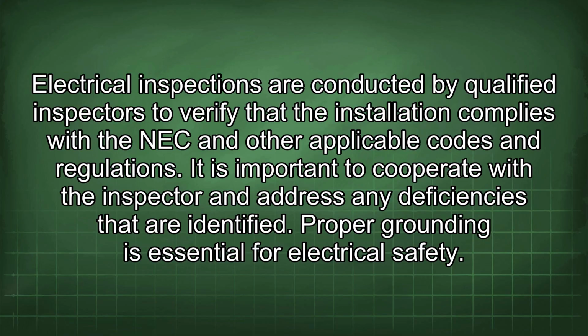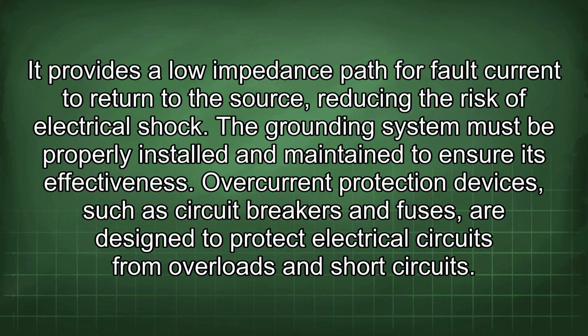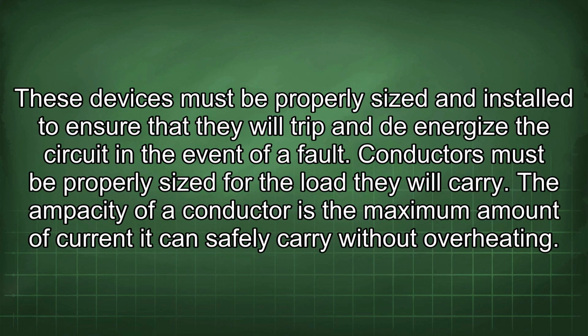Proper grounding is essential for electrical safety. It provides a lower impedance path for fault current to return to the source, reducing the risk of electrical shock. The grounding system must be properly installed and maintained to ensure its effectiveness. Overcurrent protection devices, such as circuit breakers and fuses, are designed to protect electrical circuits from overloads and short circuits. These devices must be properly sized and installed to ensure that they will trip and de-energize the circuit in the event of a fault.